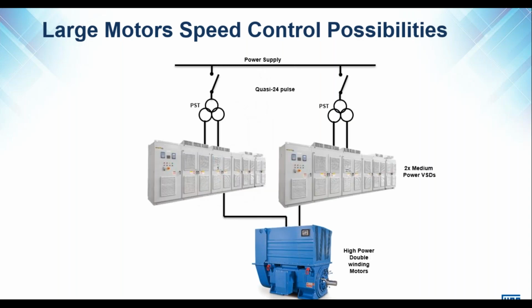But we can also move the complexity from the VSD to the motor. This is an example of an application where the motor had double windings. We had one VSD supplying one winding and the other VSD supplying the other winding. This particular application is not very common, but it had two different load profiles. In one load profile, we would energize only one winding, and only when the load demand from the process increased would we need to energize both windings of the motor.